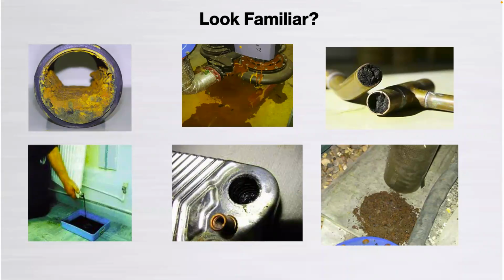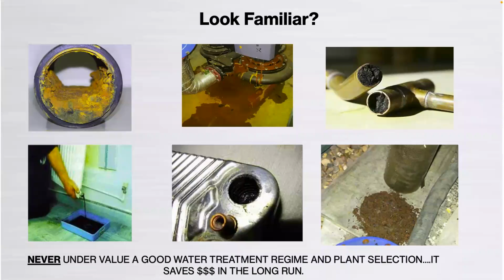So the most important, I would actually say, yes, the most important time of system water cleanliness and water treatment is actually the very beginning. Because if we don't get all that stuff out at the very beginning, throughout the facilities management life cycle of the system, it's just going to keep moving around, and it's very difficult to maintain a good level of water quality and water treatment at that point. So designing systems is really important, with good flushing velocities, line size flushing velocities at terminal locations, etc. So never underestimate a good value of water treatment.